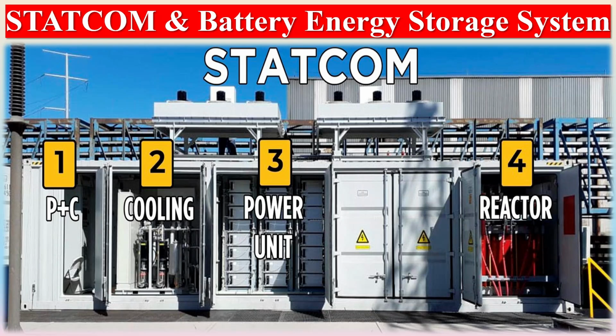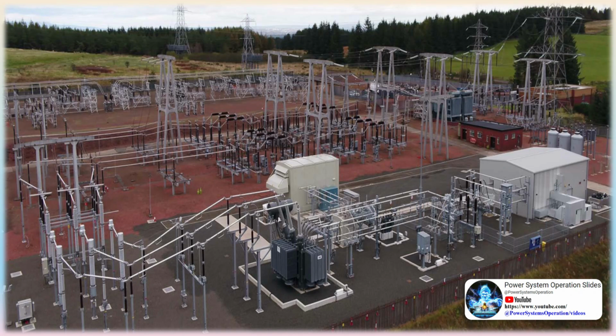A typical STATCOM configuration consists of multi-level VSCs based on IGBTs, phase reactors, and a step-up transformer. It is shunt-connected to the grid. The reactive current is provided or absorbed by producing a controlled internal voltage waveform.